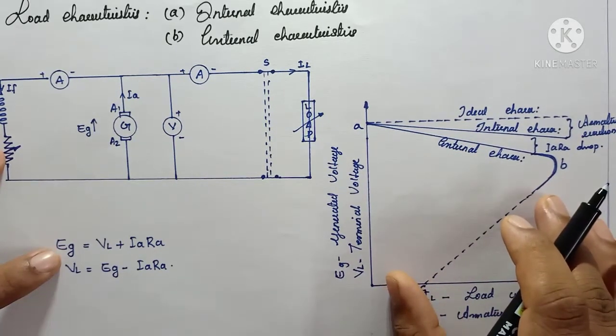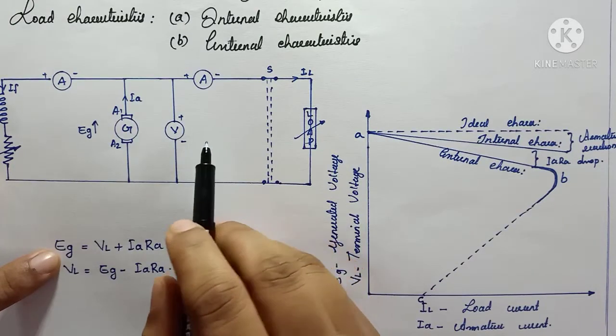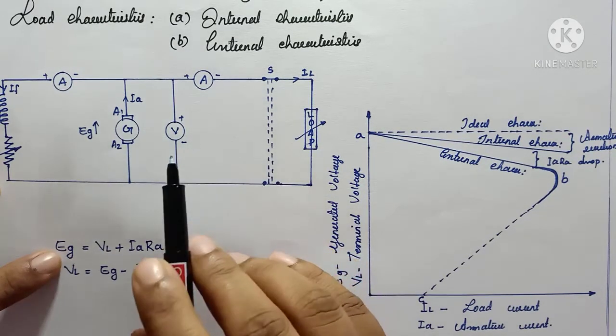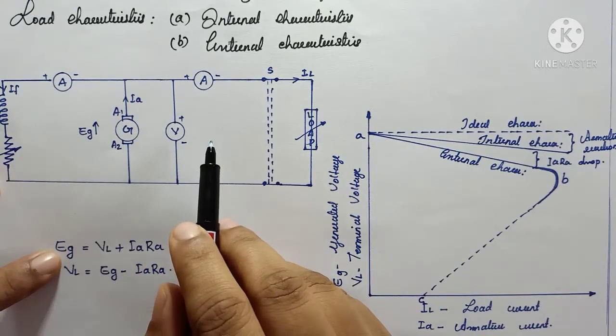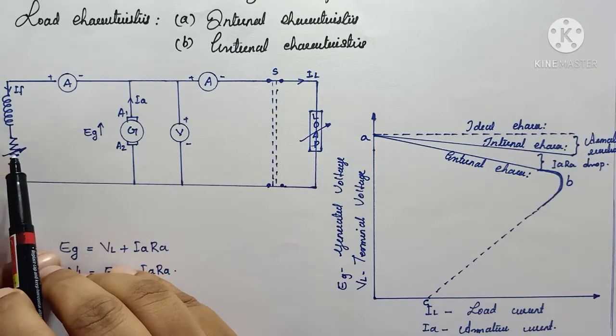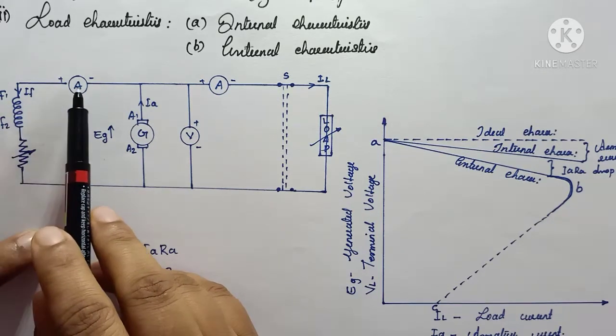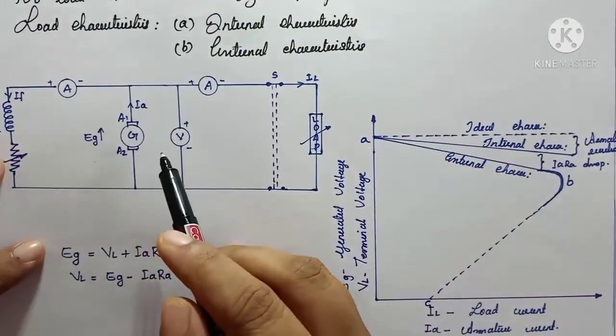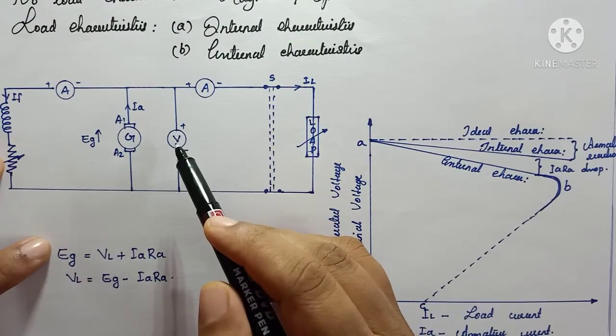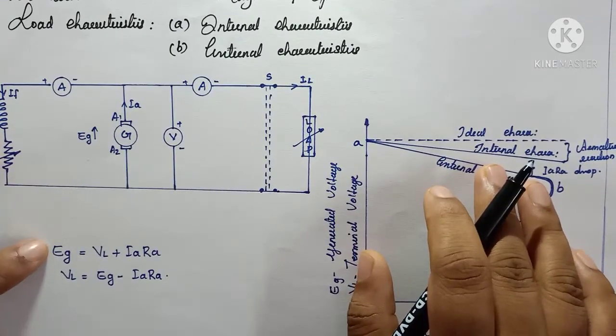When we consider the external characteristics, we must first ensure that the generator is running at a constant rated speed and that the field current is kept constant. The field current can be kept constant using a variable rheostat, and its value is monitored using an ammeter. The voltmeter measures the terminal (load) voltage, and the ammeter reads the load current as we load the generator from no-load to full load.